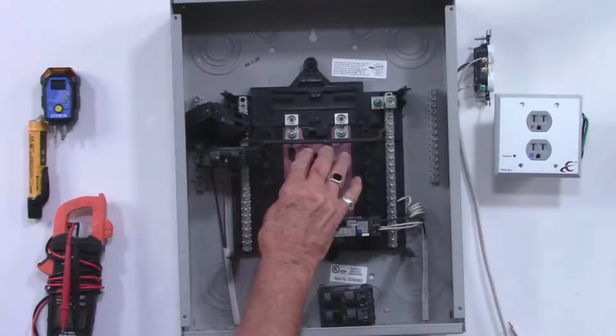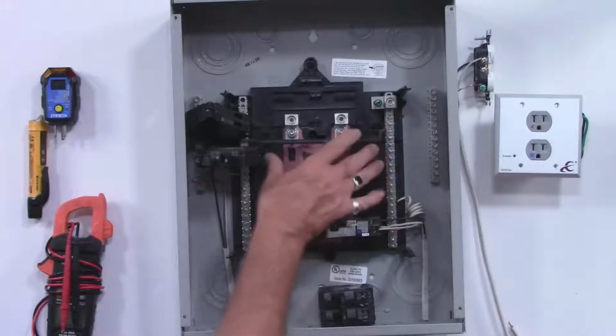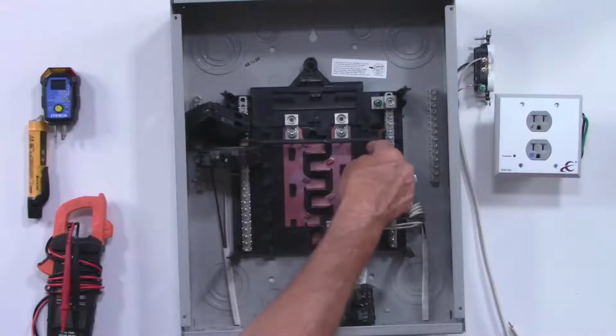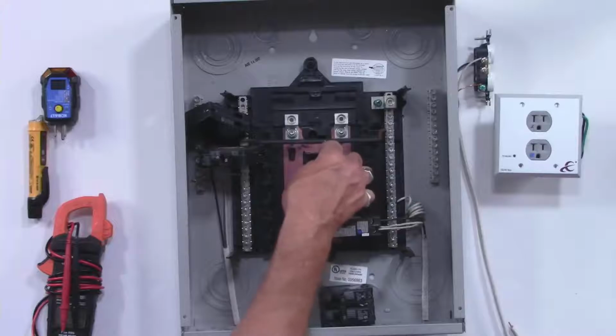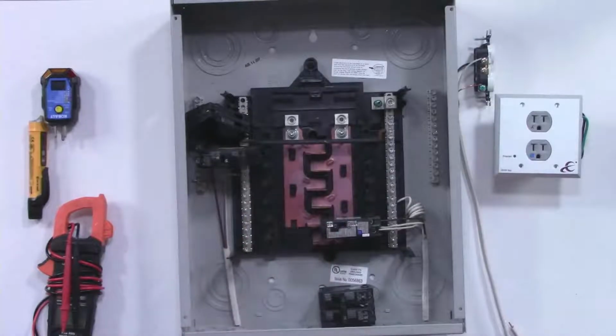These two would give us 120 on either side. If we went to these two, then we get 220 across - that's how we do the water heaters. I want to make sure I understand this correctly: if I have a load on A side number 1 and a load on A side number 2, they're still on the same circuit.